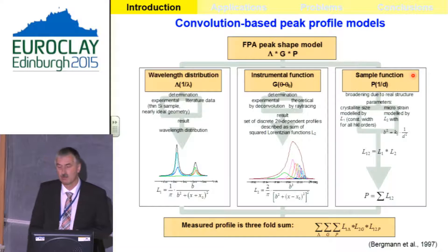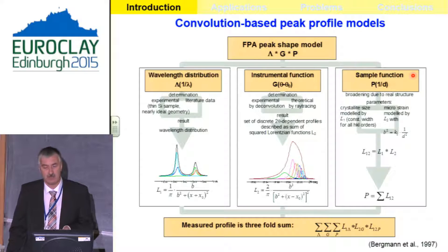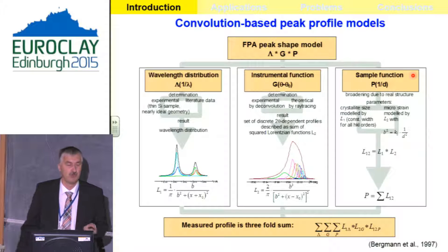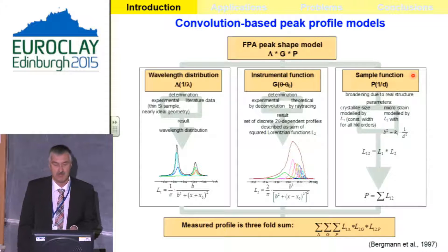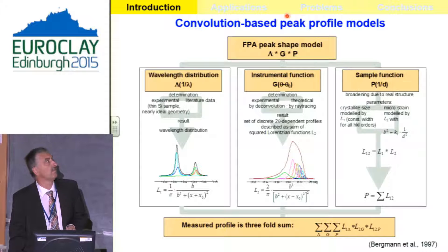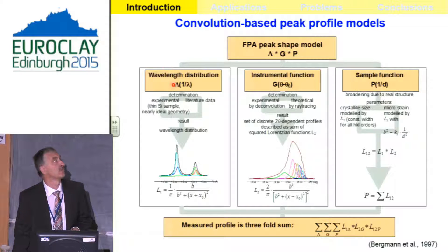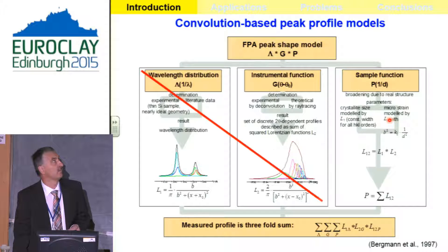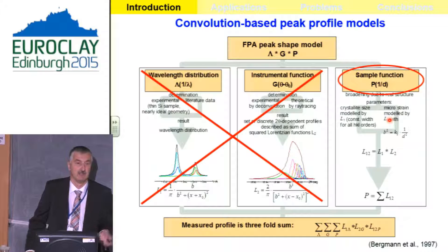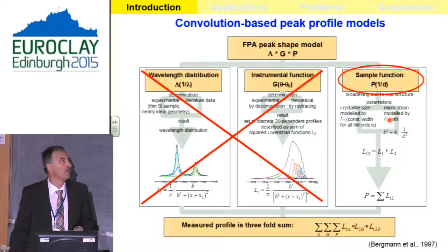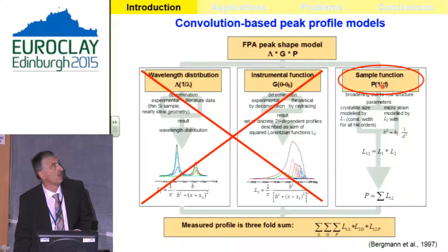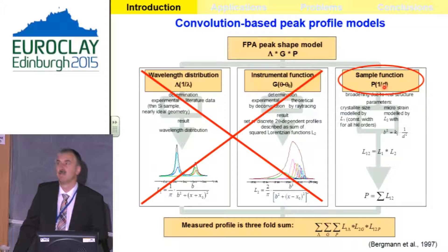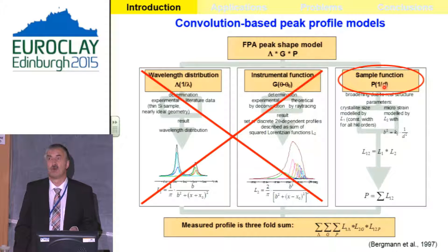During the development of new software, new methods and models were also introduced. One example is the so-called convolution-based peak profile. We know that a peak is defined by influences from the wavelength distribution, the geometry of the instrument, and the real structure of the sample. If we can calculate the instrument part beforehand, we can focus entirely on the sample function in reciprocal space, which makes the creation of models quite easy.